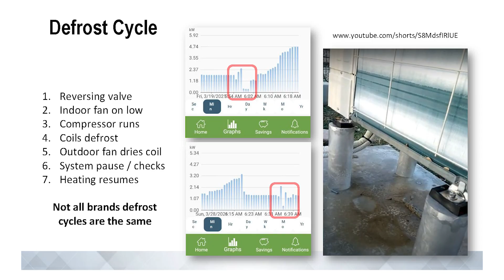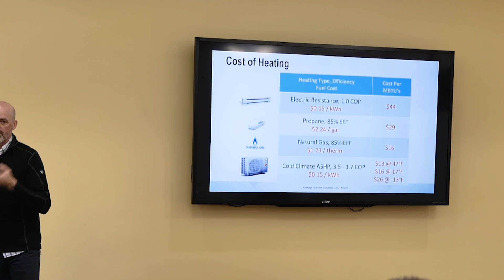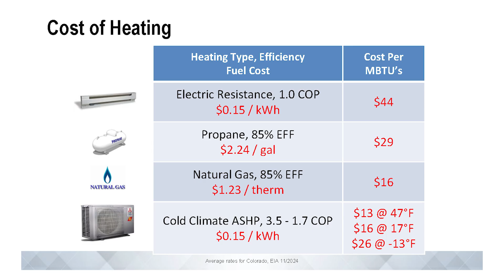Now for costs: top line is electric resistance, propane, natural gas, and then heat pumps. The right-hand side is cost per million BTUs — a therm is 100,000 BTUs, so a million BTUs is 10x that. We might figure $4.40 to run one therm's worth of electric resistance, which is expensive. For propane it might be around $2.90 a therm, depending on the price you pay, time of year, and efficiency. This is basically 100% efficient, but I'm putting in 85 here because of steady state versus cycling effects on propane furnaces, etc.